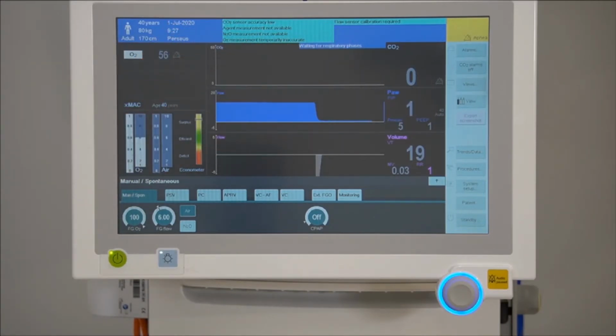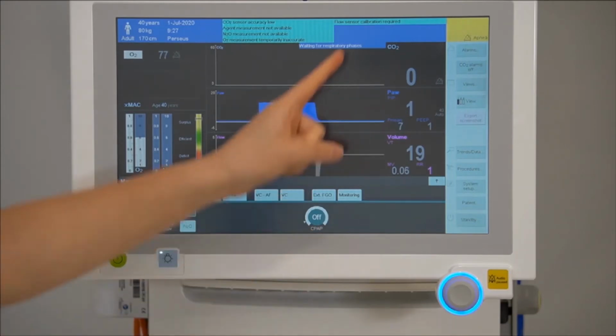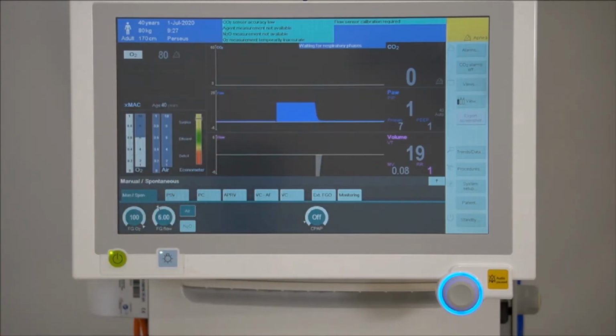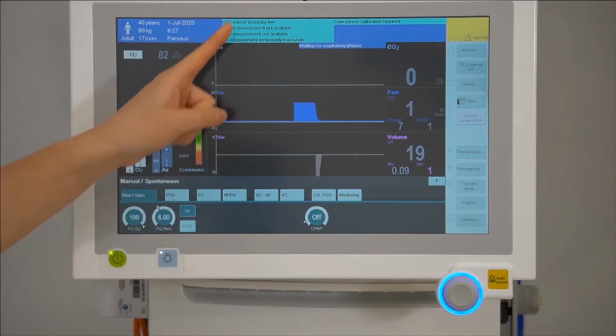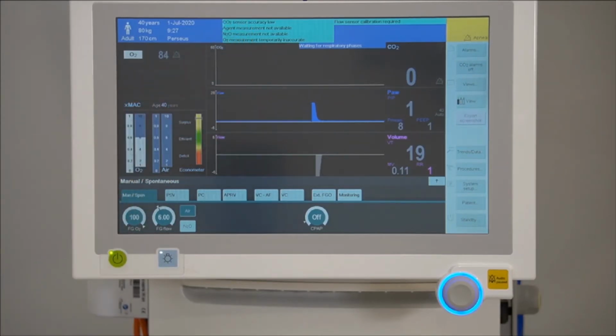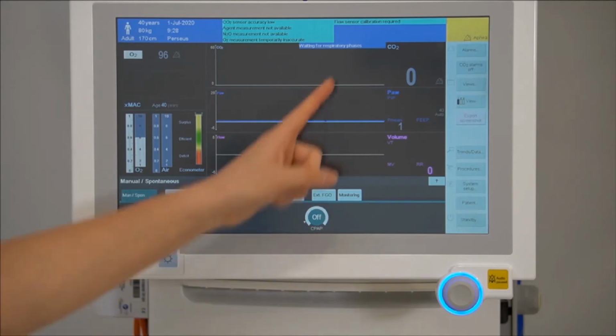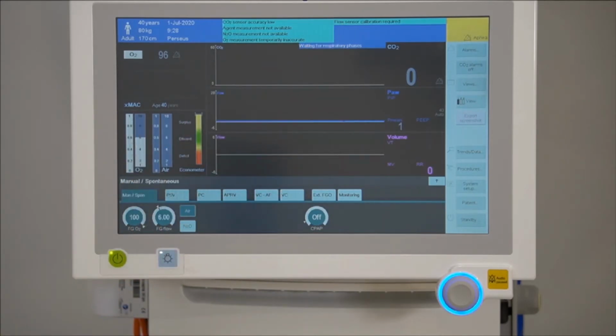Here you can see some technical and advisory messages being displayed in blue. This is because a system test has not yet been performed. To calibrate the flow sensors, this is done during a system test. The messages regarding gas measurement will appear until the gas bench has warmed up and been calibrated. Despite the flow sensors not yet being calibrated, it is still safe to use the device and mechanically ventilate the patient. To calibrate the flow sensors, a system test is required.